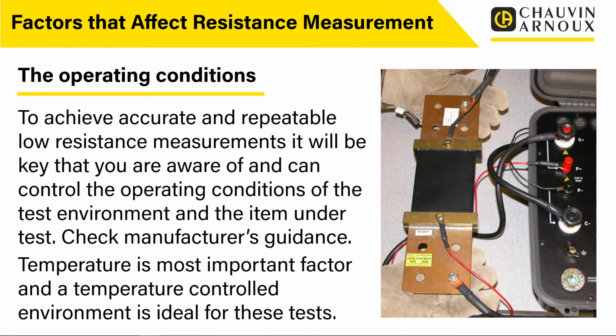Operating conditions. Now, this covers a hell of a lot of things. To achieve accurate and repeatable low resistance measurements, it will be key that you're aware of and can control the operating conditions of the test environment and the item under test. Check the manufacturer's guidance. This is important, and it'll be in the manuals for all of our products. If you have a look in there, it will give you the operating conditions: the temperature range, the humidities, the altitudes, all sorts of things. The operating range of those pieces of equipment.